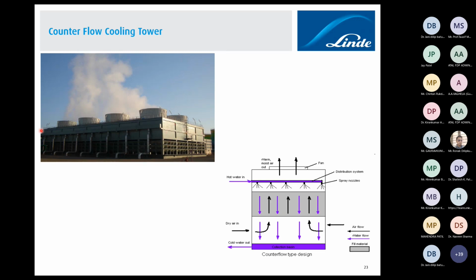The second thing you can see is that it is not completely open from bottom to top. In the top portion it has fill material, whereas on a cross flow it was on the side, right? So here in the closed portion you will find fill material, and the open louvers on all four sides are used for air movement. And the return water is fed up to the top because you want to utilize this line pressure to create the flow, to create the pressurization effect. This is why counterflow cooling towers are more effective compared to cross flow, and you will also find a smaller footprint. So this is the main advantage of this cooling tower.